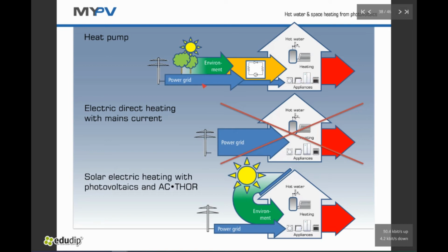And now you can say, okay, but I can combine a heat pump with a PV system. Yes, you can do, but then you have 2 expensive systems in your building, and a heat pump fits not very good for PV systems, because you cannot control the power input for the compressor and the heat pump linearly. This is a static power input. While we can adjust the power of an immersion heater, of a resistor, every second new on a new stage. So this is PV ready. And in many projects where the sum over the year of the power grid import is smaller than in the compared system with the heat pump, we are talking about the more ecological solution here.